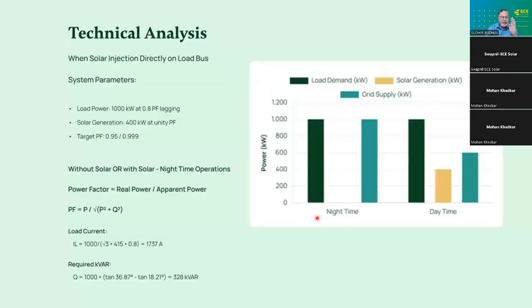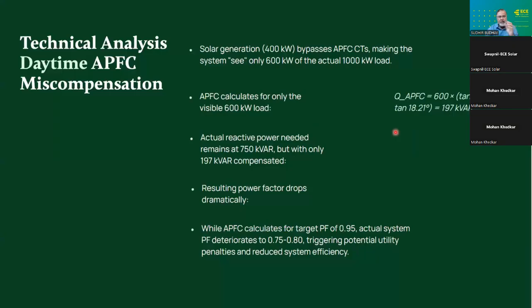So just see, with solar or without solar at night time. Suppose my demand is 1000 kilowatt. I'm taking power throughout the night without any solar power injection, from the distribution company or grid supply. Suppose my power factor is 0.8 lagging, then I'll require 328 kVAR to compensate that. But what happens during daytime? In the daytime, I start injecting real power into the system. Now I'm injecting 400 kilowatt from solar and drawing 600 from the grid. As a result, my CT senses only the 600 kilowatt load and activates only 197 kVAR.